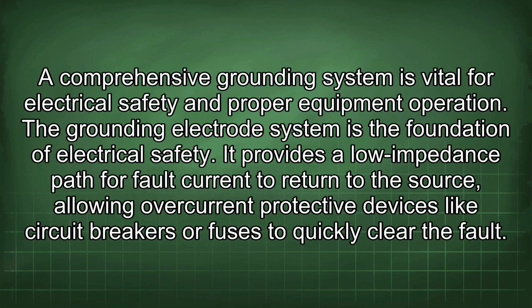A comprehensive grounding system is vital for electrical safety and proper equipment operation. The grounding electrode system is the foundation of electrical safety. It provides a low impedance path for fault current to return to the source, allowing overcurrent protective devices like circuit breakers or fuses to quickly clear the fault.